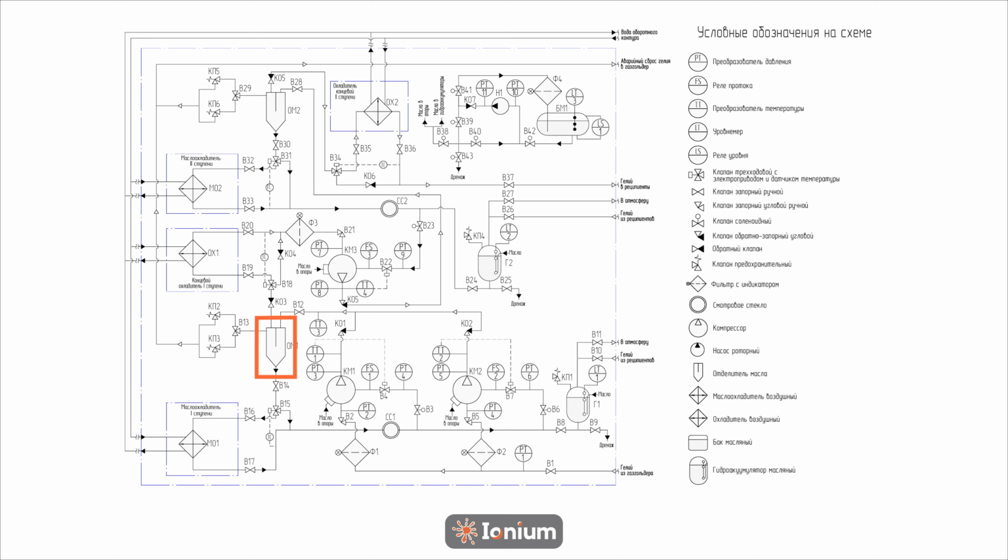At position OM1, the oil is efficiently removed. Oil from the separator is channeled into the water oil heat exchanger at position MO1, cooling it to about 28 degrees Celsius. It is then injected into the machine's working chamber at approximately 3.8 bar.